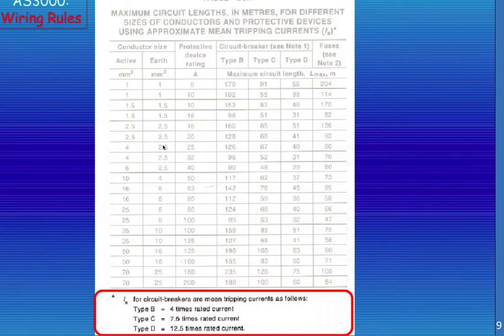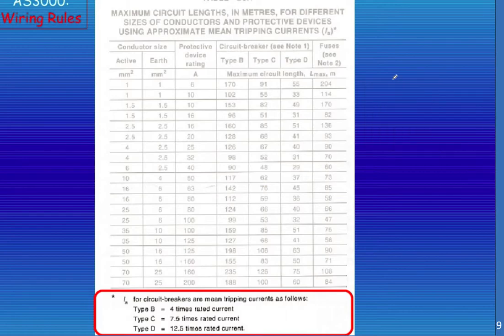So the first thing we need to understand is we have this table from AS3000 called table B5.1. And the first thing you'll notice is that we have conductor sizes over on the left-hand side, and we've got our active conductors in square millimeters, we've got our earth conductor in square millimeters. Our protective device, so our circuit breaker rating, effectively that's what that is, here in this column in amps.